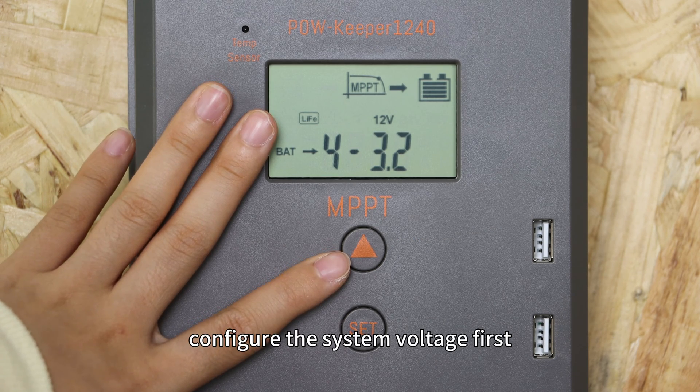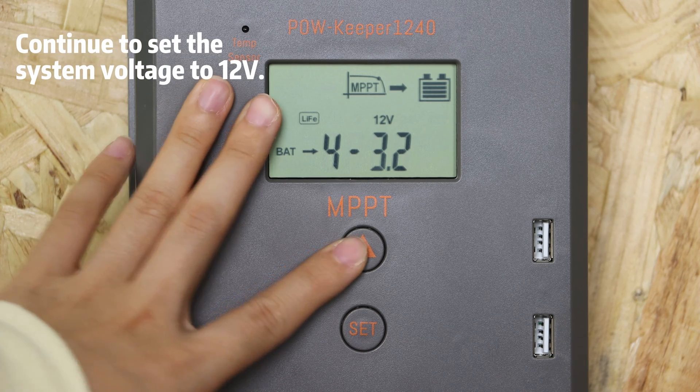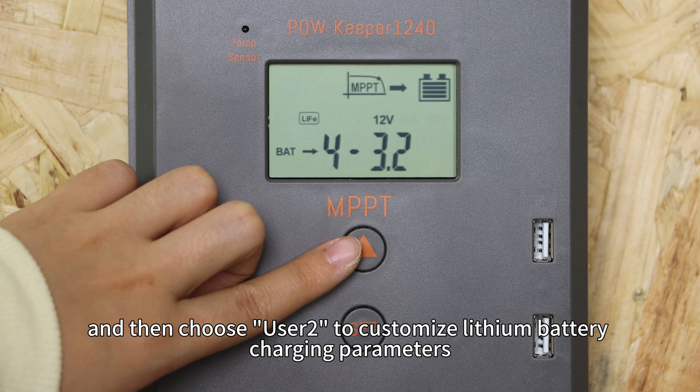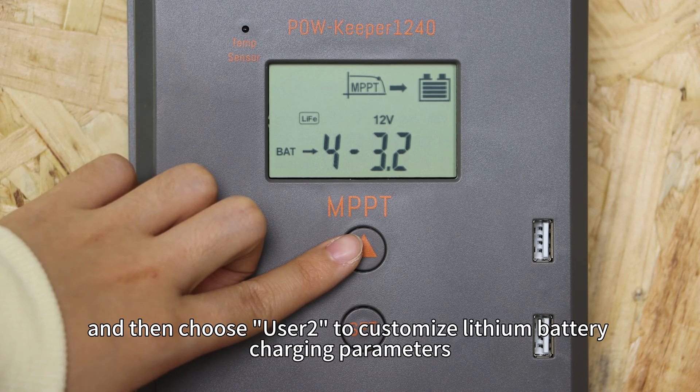For the fourth scenario, if your connected lithium battery does not match any of the available battery types, configure the system voltage first, and then choose User 2 to customize lithium battery charging parameters.